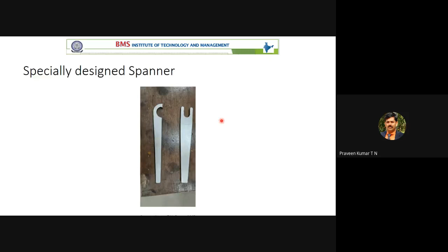Here, one collet you rotate in one direction, and using one more spanner, you rotate the other in the opposite direction. That is how the specimen is mounted. It is almost like holding a scale with 2 hands. It should be gripped properly, because this specimen will run for a few hours or few days to test the life of the shaft or beam. These are special spanners designed only for fixing the specimen, especially for this particular Ducom make fatigue testing machine.